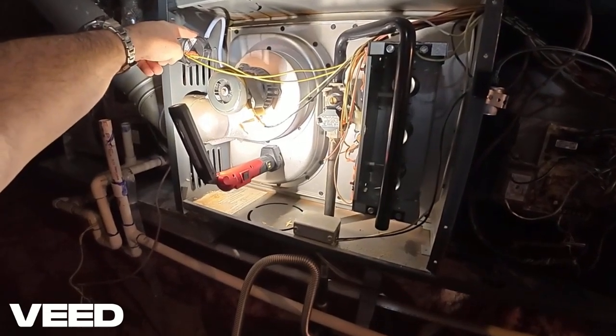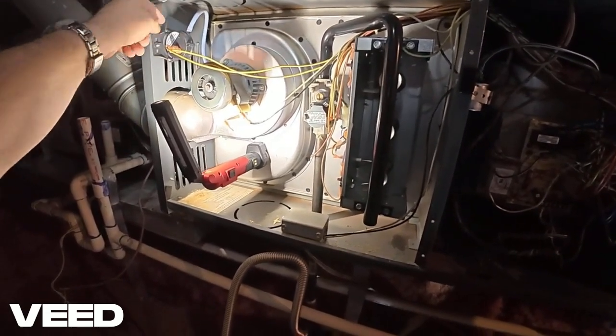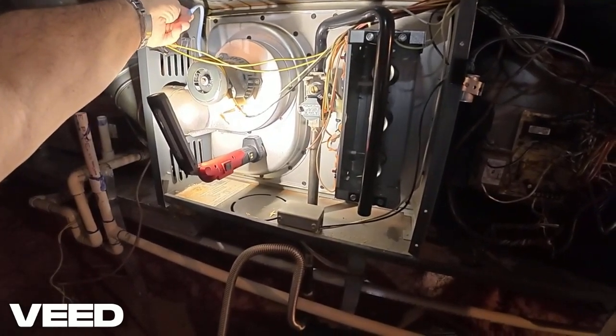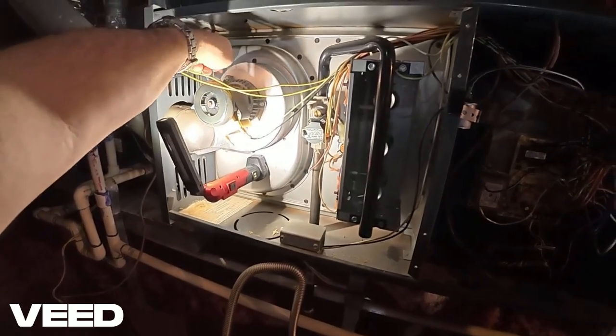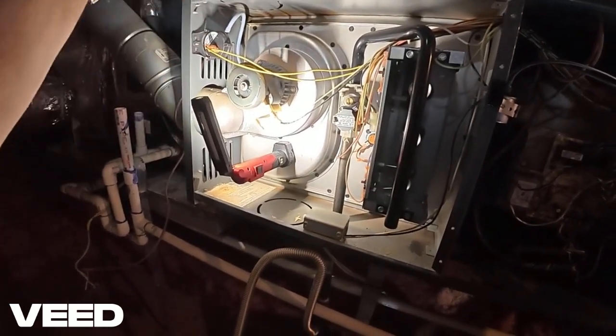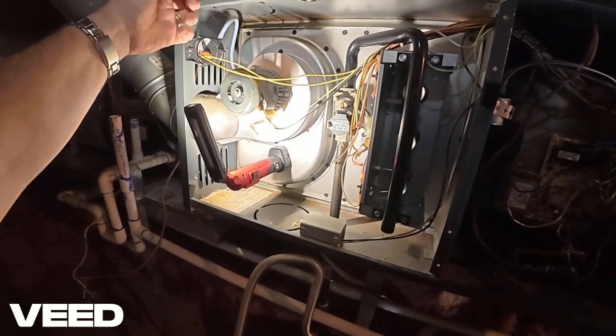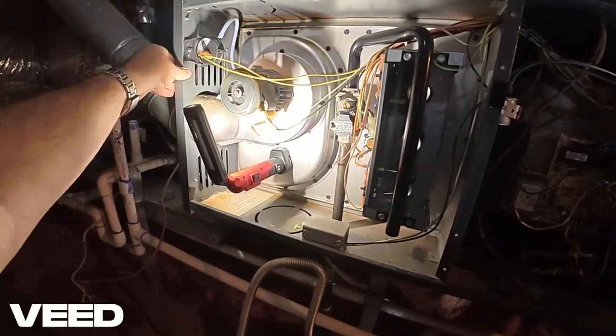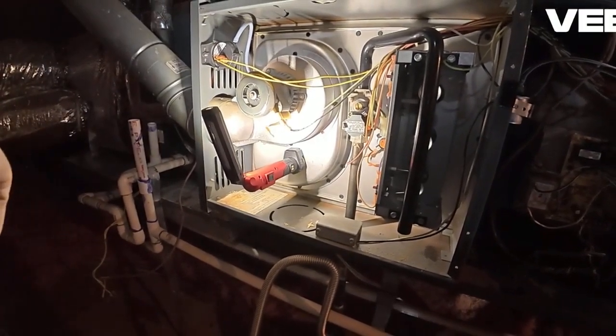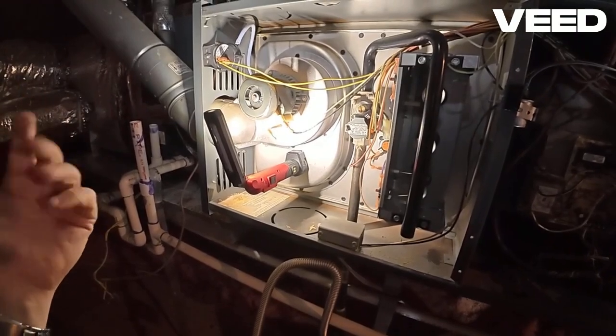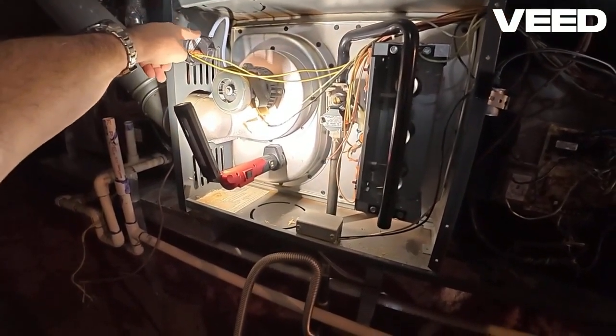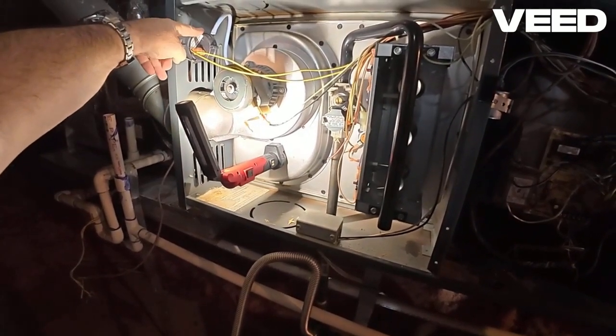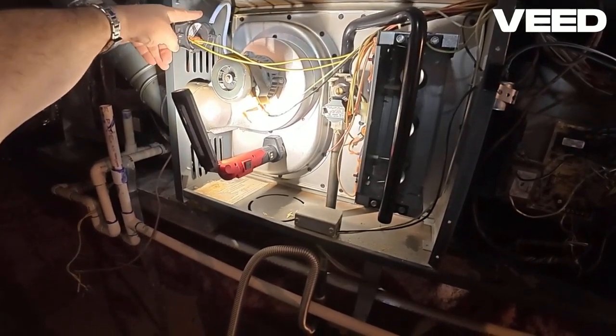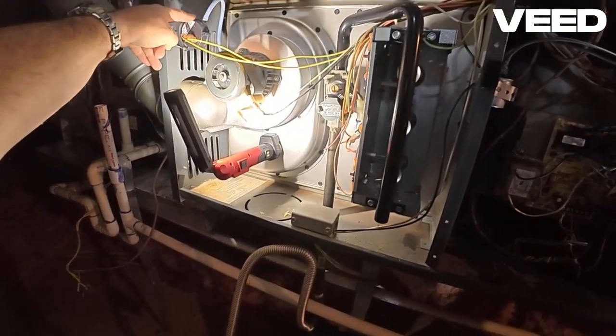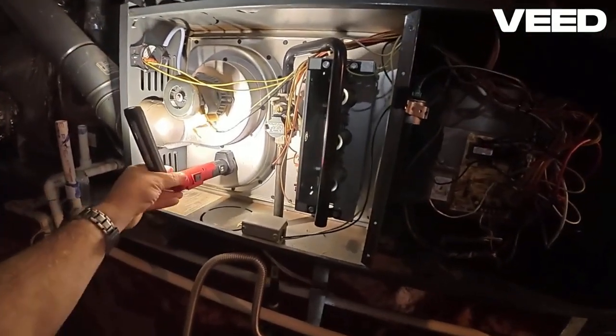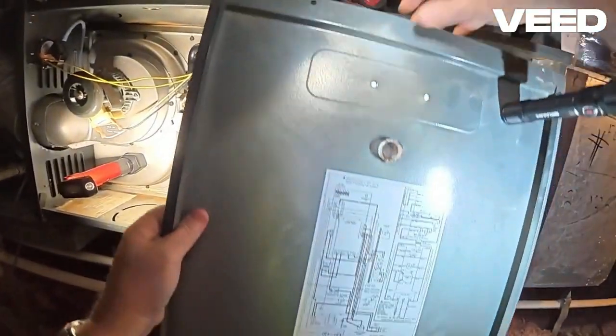If it's not closing and it's stuck open, often, not always, but it could be a problem in this hose, or where the hose connects, there's a very thin orifice, or small orifice, and that often gets clogged up with debris and needs cleaned out. So that could be the result of it stuck open. Could also be defective and as well stuck closed. So that's the pressure switch alarm.